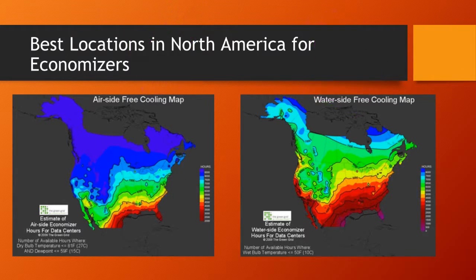Over here on the right side of the screen, you're going to see it's our water side free cooling map. Now, I don't know if we stated this earlier, but air side is going to be a lot more efficient than your water side. So you can see on the map here, it's going to reflect on the image here. You can see that that red line is creeping up on the United States a lot further than over on your air side. Red line here is only in like the Carolinas compared to over here, red's reaching Pennsylvania. So it's just not as efficient a way to save energy with the water side. Up in the north here, it's a little better. You're not really seeing the blue until you hit Canada.